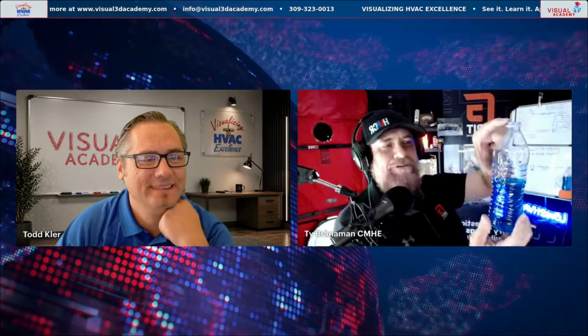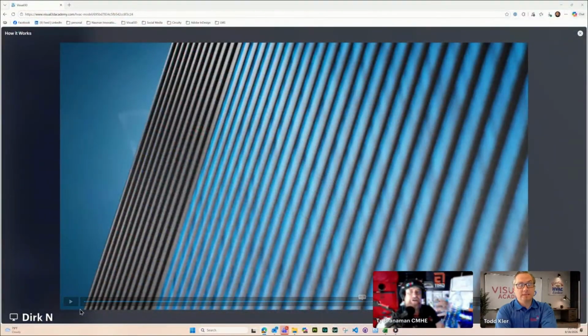On the other hand, if you had that PH diagram earlier talking about where it's changing state, if I want this much superheated vapor, but I have this much superheated vapor, well, I've got way too much superheated vapor. So there's not enough refrigerant changing state. This is why I'm doing it with a water bottle. You guys are doing it much better with your visual 3D because you can actually see where it's changing state. And this refrigerant changing state, that is the magic of it absorbing heat. That's 970 BTUs for every pound of water changing state.